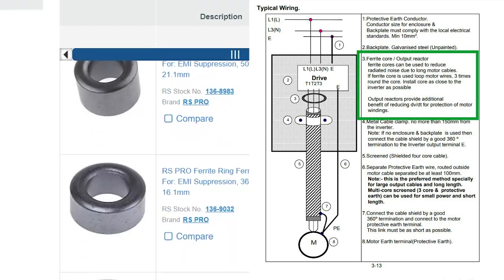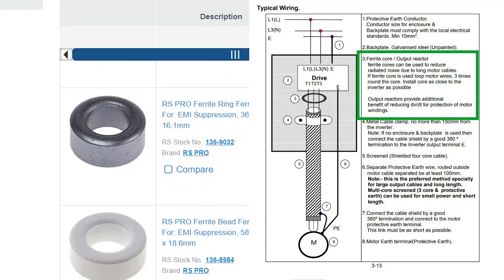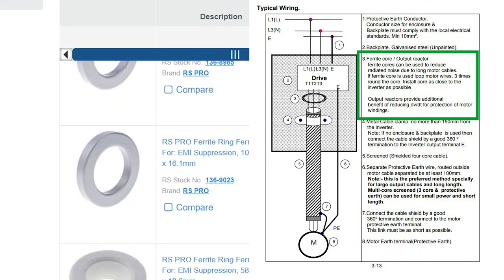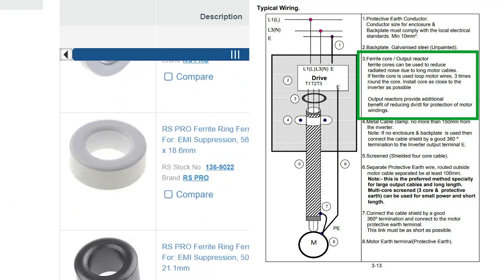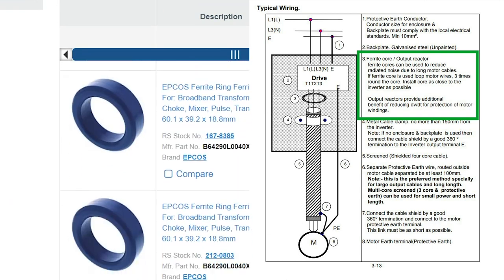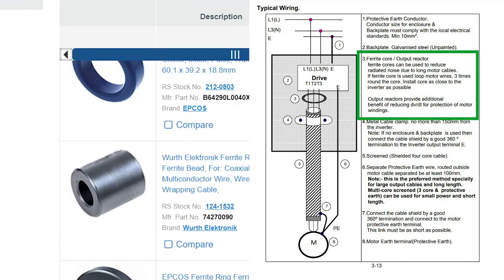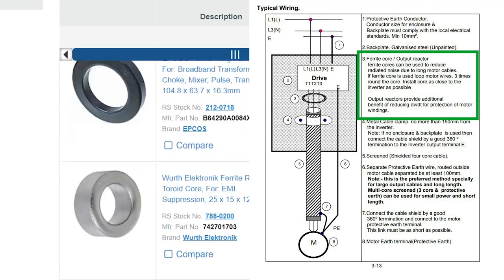I have the ferrite core, but you only have to coil the three motor cables three times through the core and not the earth wire.